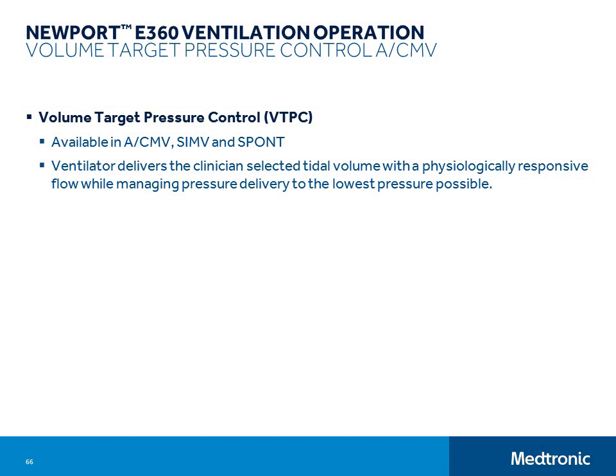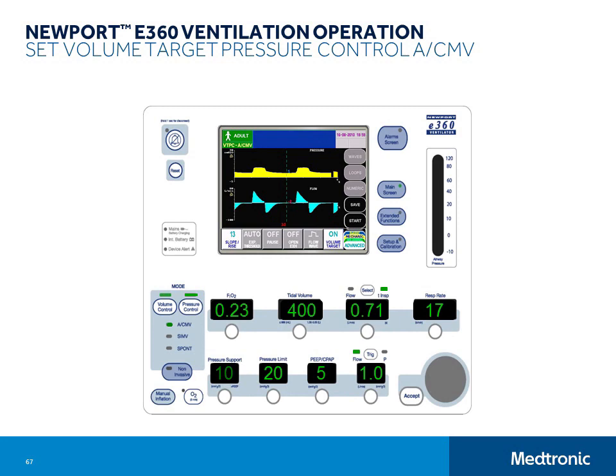For volume target pressure control ACMV, set pressure control or volume control ACMV on the control panel. Then set volume target on in the advanced data set. Notice that both the pressure control and volume control breath type indicators light up, and both the pressure limit and the tidal volume displays light up. The tidal volume setting determines a target value for volume delivery, and the ventilator servo controls the pressure control level in order to deliver that set tidal volume. The pressure limit is the maximum pressure that the ventilator will use in order to attain that tidal volume. So you need to set the pressure limit at the maximum target pressure above ambient that is acceptable for the patient. Also note that the open exhalation function is not available when you turn on volume target. You need to turn off volume target if you wish to use the open exhalation valve BPRV function.